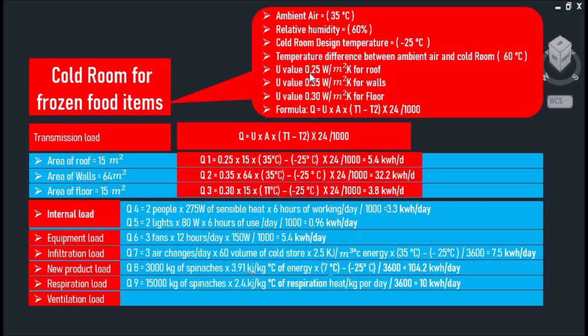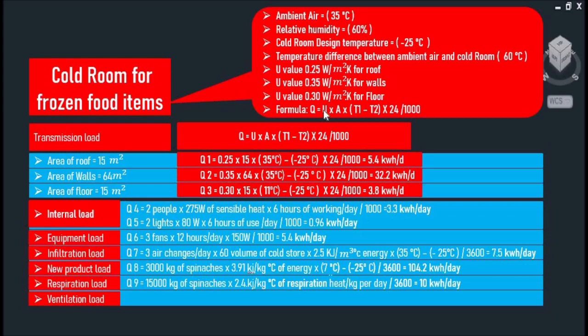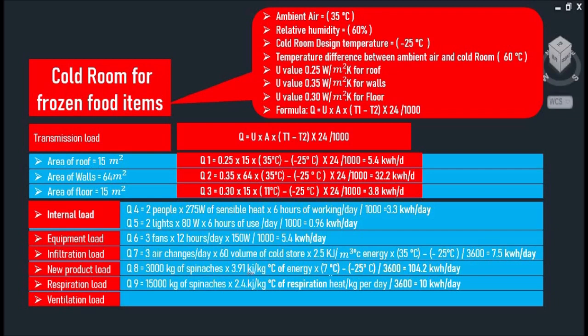With a U-value of 0.25 watts per square meter Kelvin for our roof, 0.35 for our walls, and 0.30 for our floor. To calculate the cooling load, we'll use this formula: Q equals U multiplied by A multiplied by T1 minus T2 multiplied by 24 hours and divide by 1000.